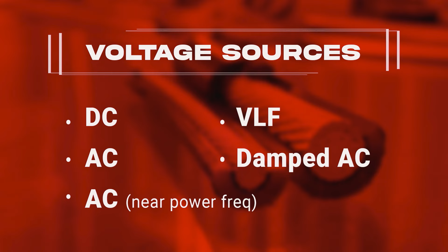Outside of the withstand testing, you have those diagnostic type tests, whether that be tan delta or partial discharge being the two most prevalent. With all of those diagnostic and withstand testing, there's various types of voltage sources that you can use for it, whether it be DC, AC, whether that AC is near power frequency or online, along with very low frequency, VLF, or damped AC, where you have just a short period where it hits near power frequency. Any of those can kind of be utilized, and each has their pros and cons.